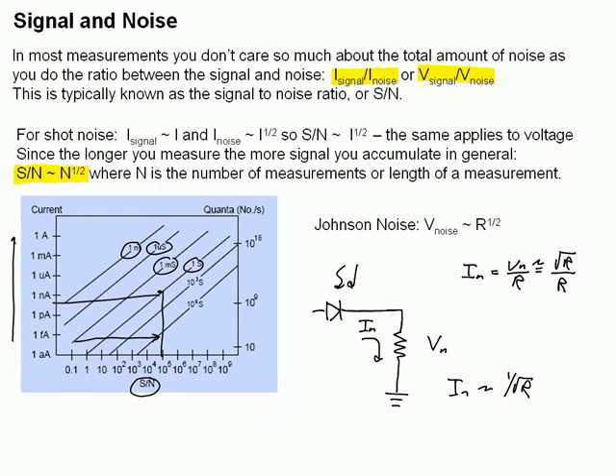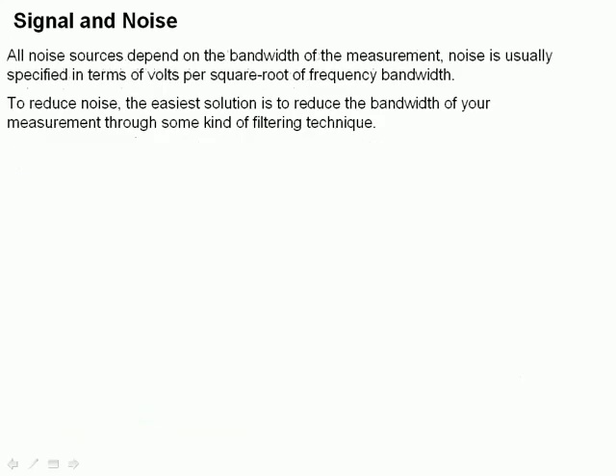What does this mean for you doing a measurement? It means if you're using a photodiode or a photomultiplier tube, both of which are current sources, and Johnson noise is important to you, you want to terminate that source with as high a resistor value as possible because small resistors lead to small denominators, which leads to increased current noise.